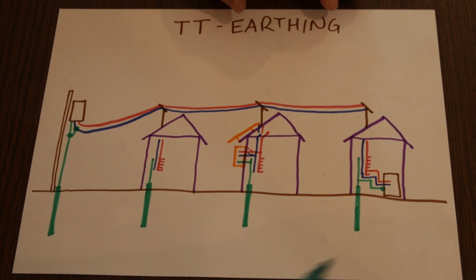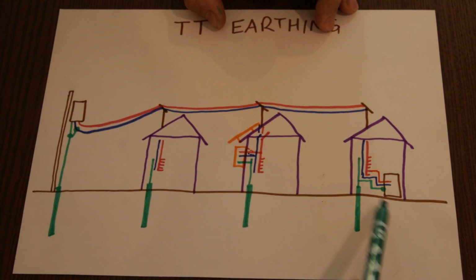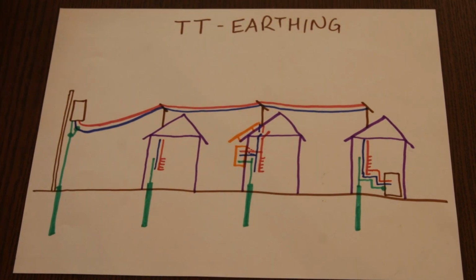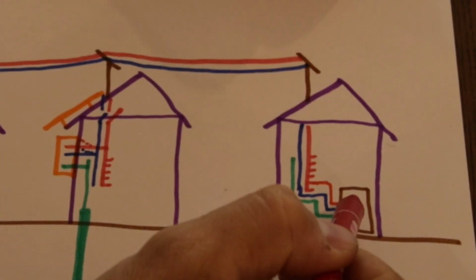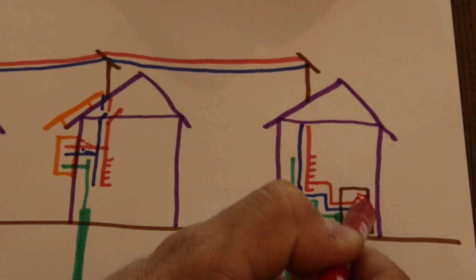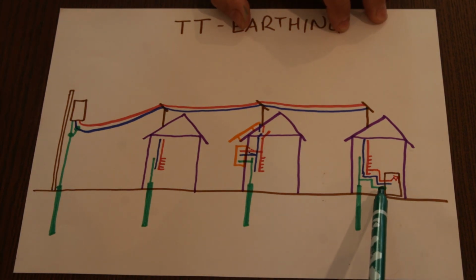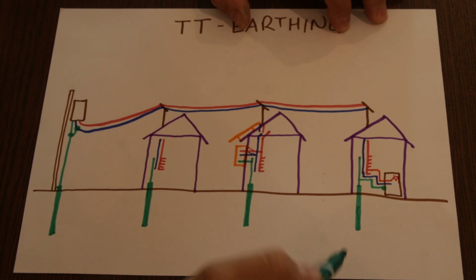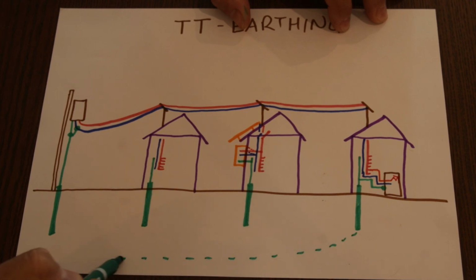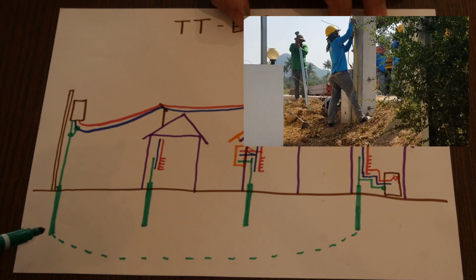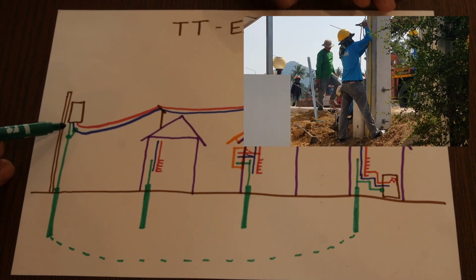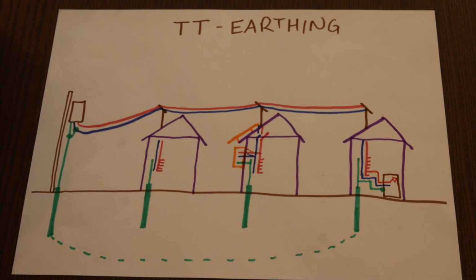So let's take a look here at our house number 3. We have our electrical appliance, and now let's say we have a leakage from our phase wire to the case of this electrical appliance. Our fault currents will now take the way via the grounding system, the earthing system, go to the rod and then go via the ground back to the transformer's grounding rod here, and now the loop is closed again because the currents will then jump over to the neutral of the transformer via the bond there, and this can then trip protective devices in our house.